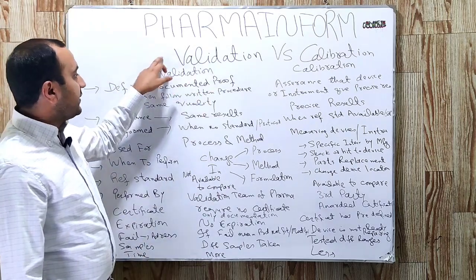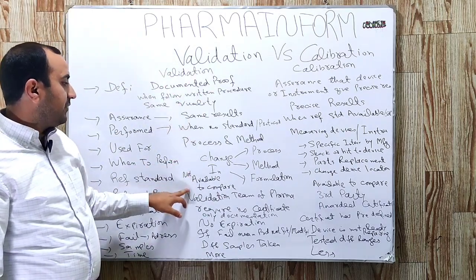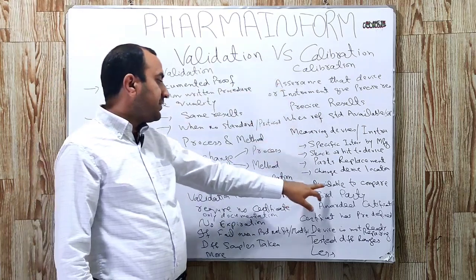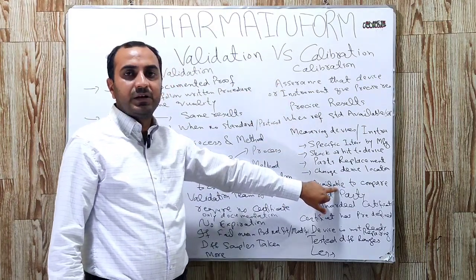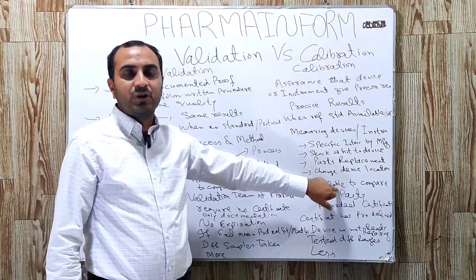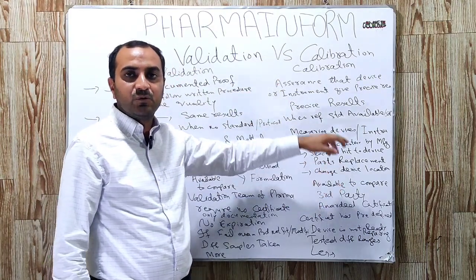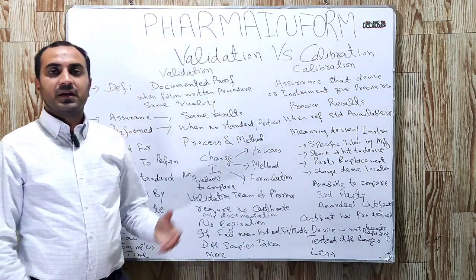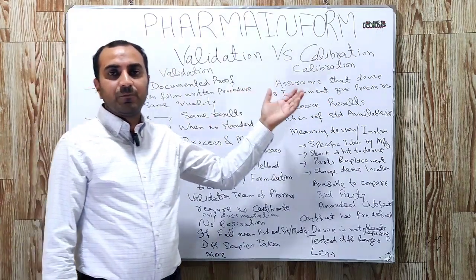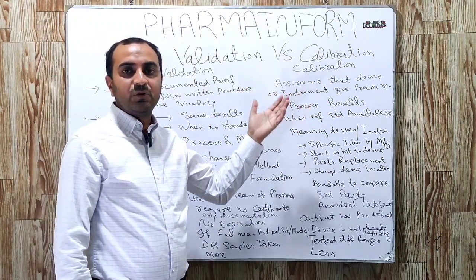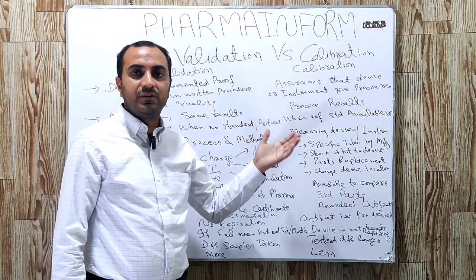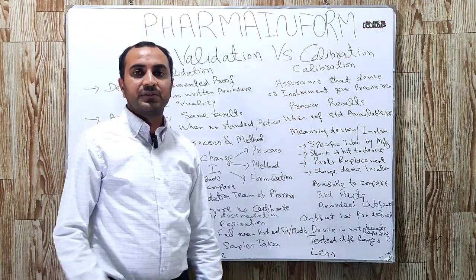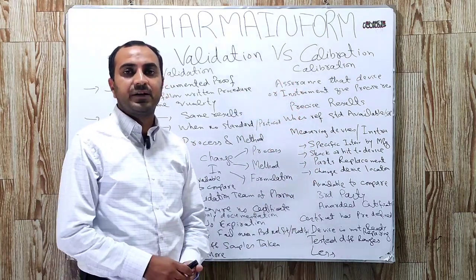Regarding reference standards: in validation, no reference standards are available. In calibration, reference standards are available and we compare the values against those reference standards. An example is calibration of a weighing balance, where we have standard weights and calibrate the balance against them.